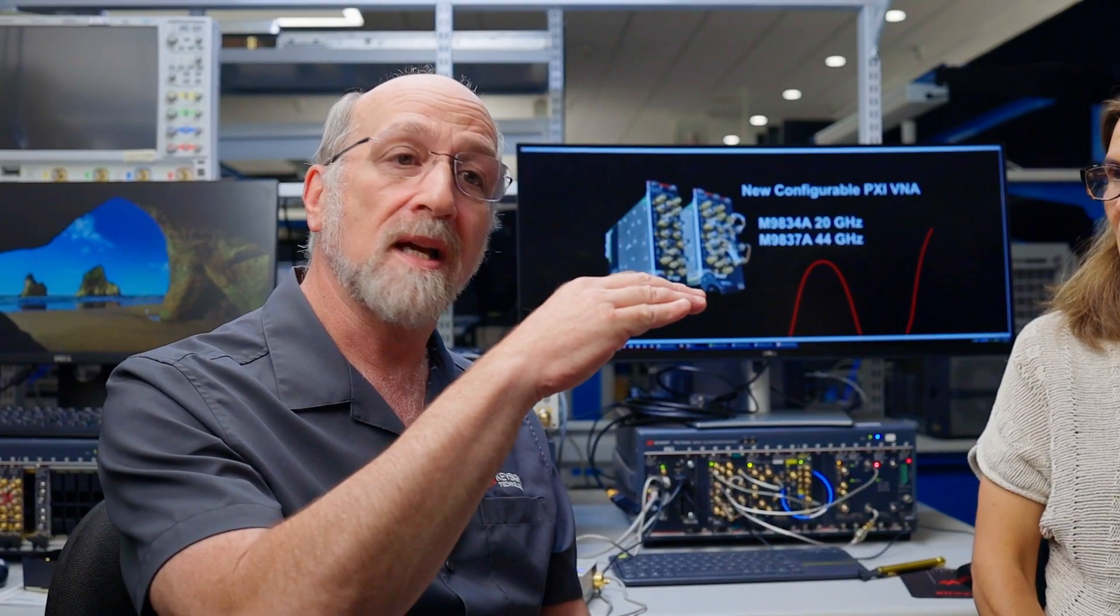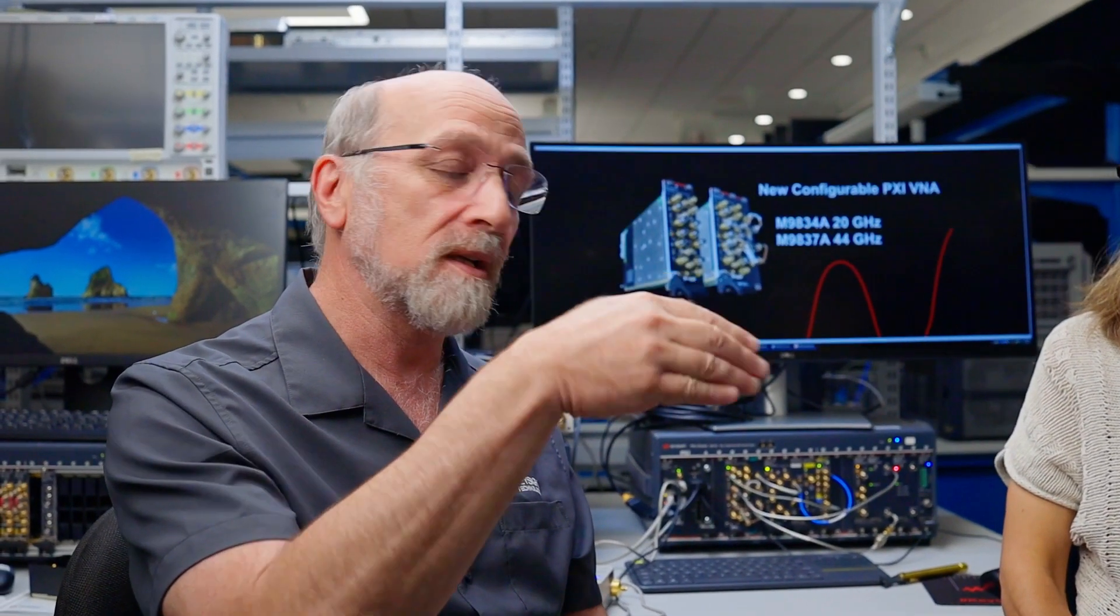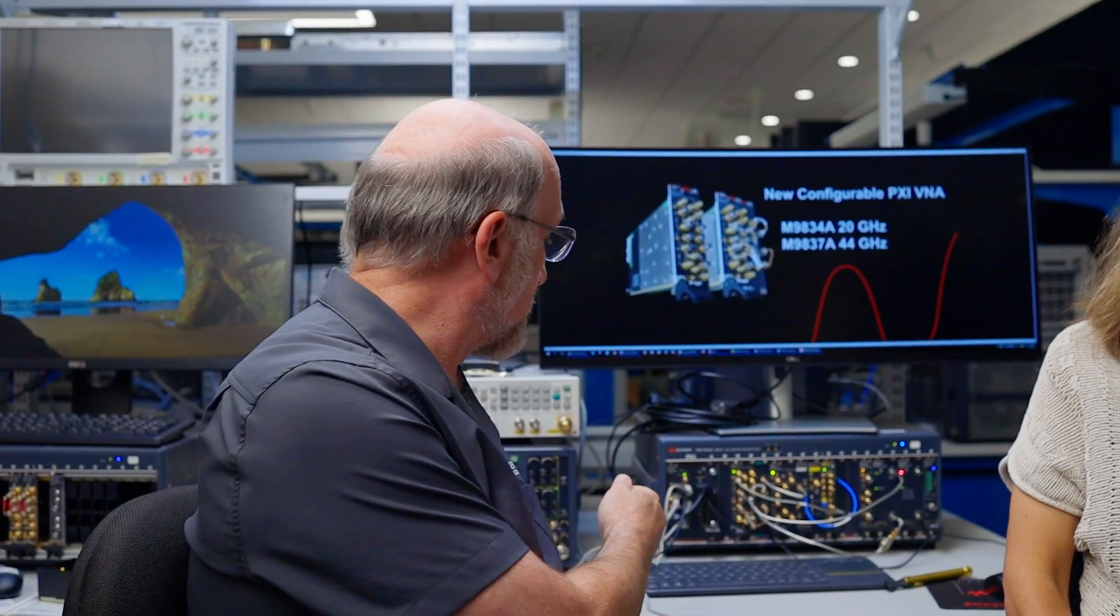We're here to talk with you about the latest addition to the Keysight Network Analyzer family, the configurable PXI VNAs. These analyzers come in 20 and 44 gigahertz models, and they're well designed for active device tests such as amplifiers and mixers. This system has about 80% of the performance of the PNA-X and capability at 60% of the price. And with the multi-port configuration, it's really suitable for manufacturing test environments.